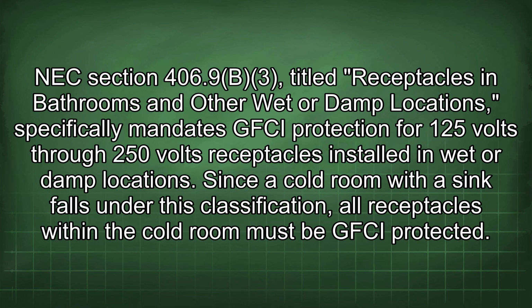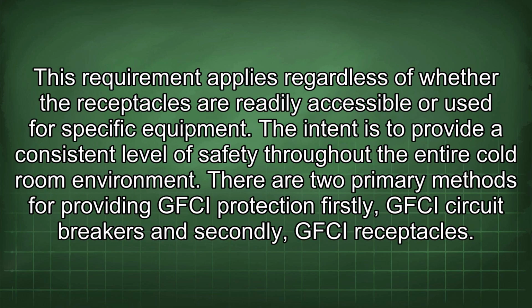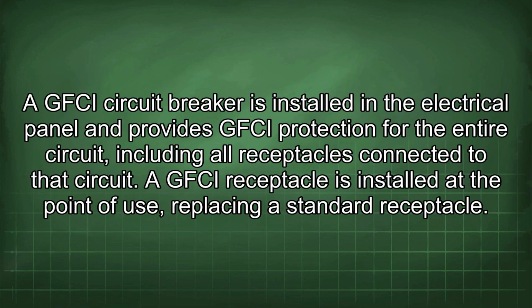Since a cold room with a sink falls under this classification, all receptacles within the cold room must be GFCI protected. This requirement applies regardless of whether the receptacles are readily accessible or used for specific equipment. The intent is to provide a consistent level of safety throughout the entire cold room environment. There are two primary methods for providing GFCI protection: firstly, GFCI circuit breakers, and secondly, GFCI receptacles. A GFCI circuit breaker is installed in the electrical panel and provides GFCI protection for the entire circuit, including all receptacles connected to that circuit.